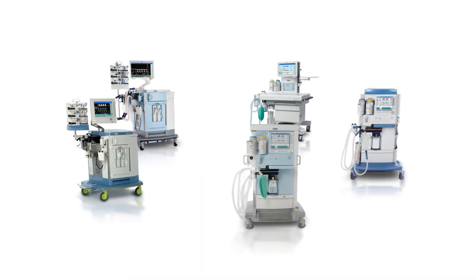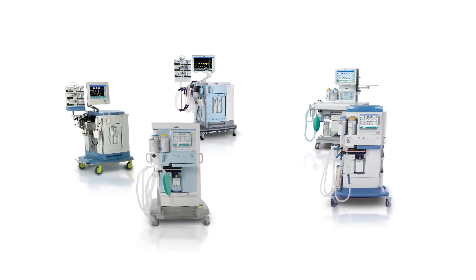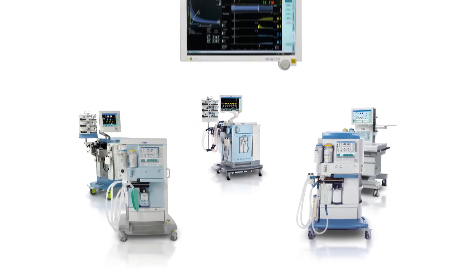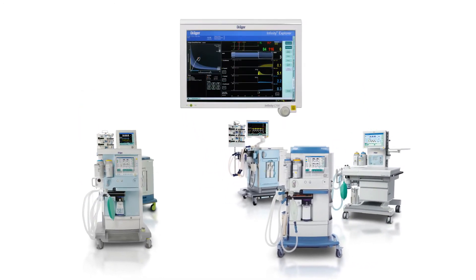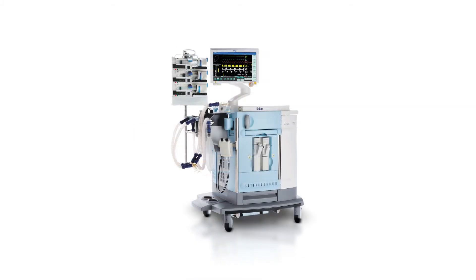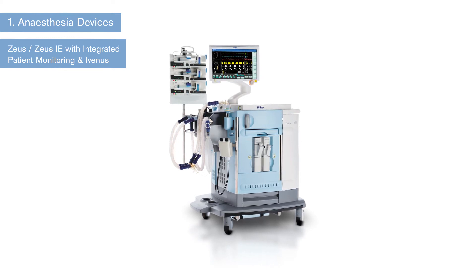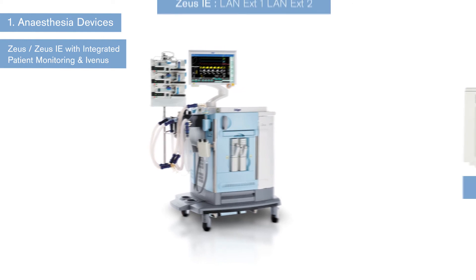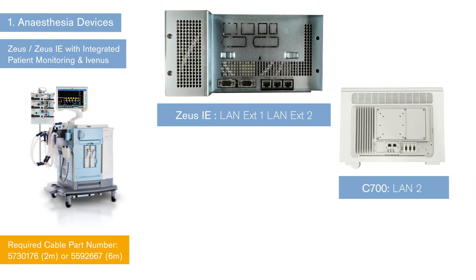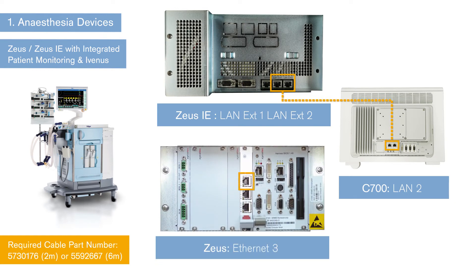We will now show you how to connect each component to SmartPilotView, describing port setups and required cables when using C700 as host. Please note, depending on device models, connectivity ports can be different. In case of Zeus or Zeus IE with integrated patient monitoring and iVenus pumps, LAN connection is used. Zeus IE LAN External 1 or 2 will be connected to SmartPilotView LAN 2. In case of Zeus without firewall, Ethernet 3 will be connected to SmartPilotView LAN 2.